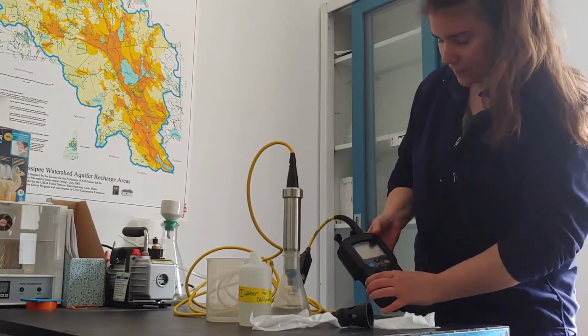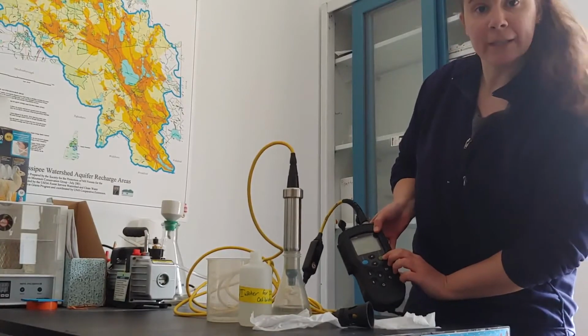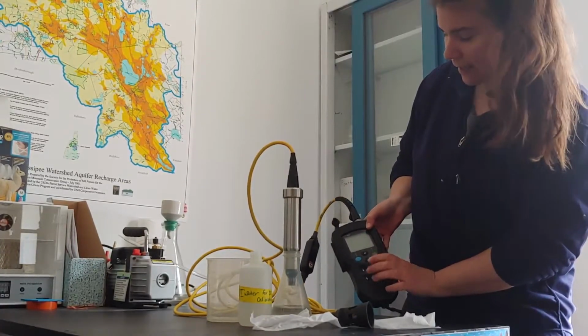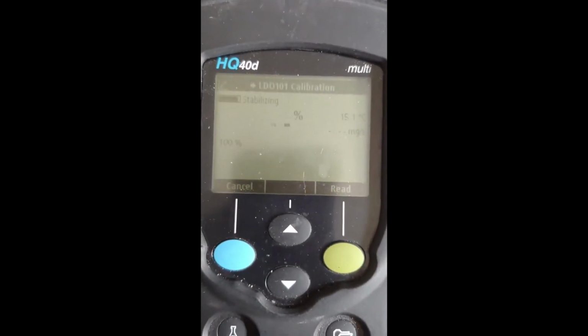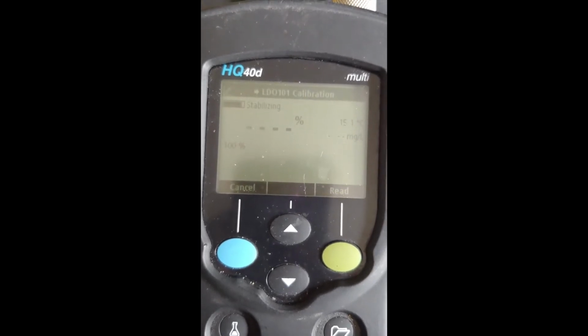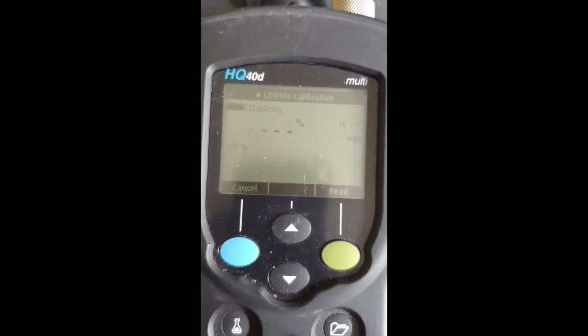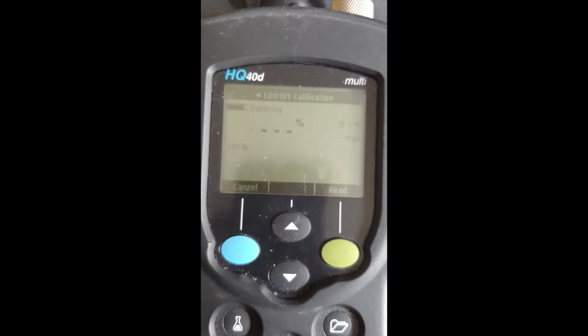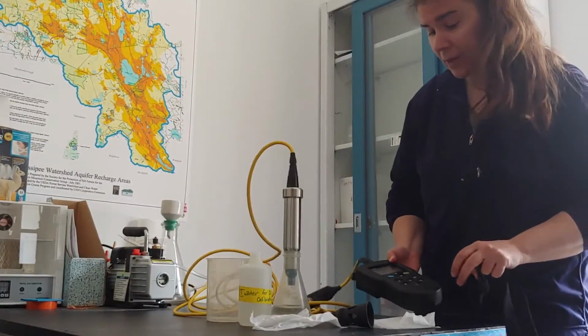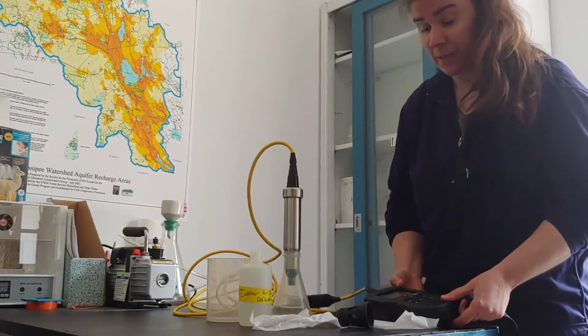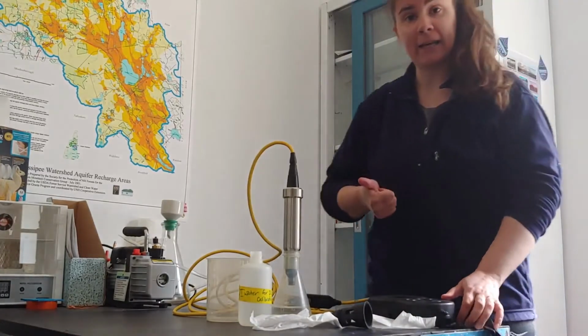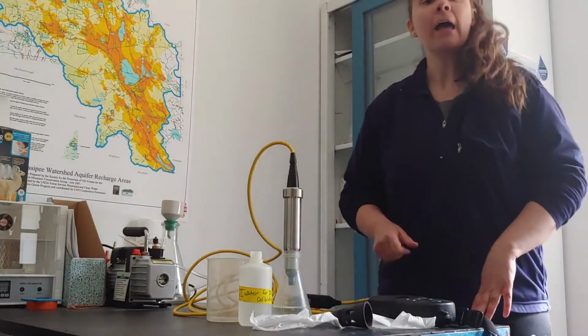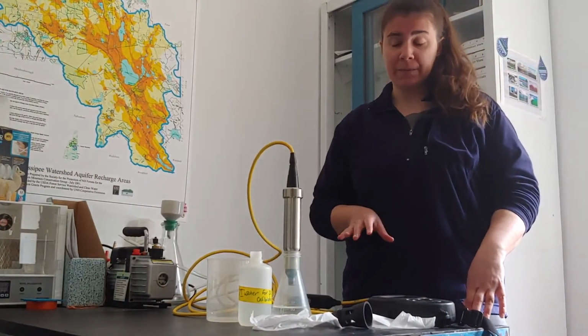Now what I do is hit the green read button, and I get a status bar that comes across the front of the screen. Once the status bar is completely filled, calibration has been completed. Calibration can take anywhere from 30 seconds to 15 minutes, so it's really important that you allocate enough time to do your calibration and that you have a little bit of patience with it.